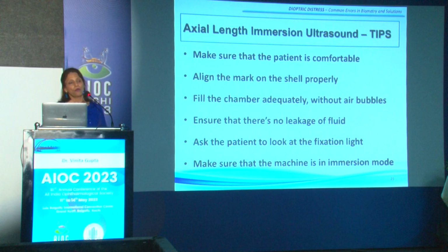Align the mark on the shell properly with the probe inside, which is submerged in the water bath there. Fill the chamber adequately without any air bubbles. That is important. Ensure that there's no leakage, so overflow should not be there. Ask again for the patient to look at the fixation light.